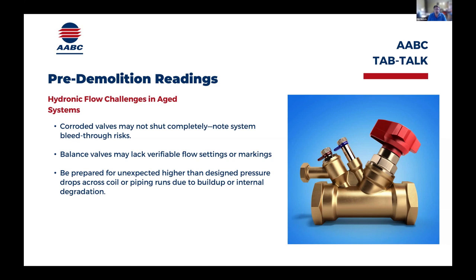Like you talked about, if the system's up and running in normal control, maybe an entering and leaving temperature of a coil along with the flow reading - if you can get both of them to match up, that's always a good thing. But there's no doubt that after 20, 30 years, there's going to be some integrity issues with the piping. Like you mentioned earlier today, the type of pipe they used 30 or 40 years ago is not exactly like they're doing now. So older equipment's definitely going to be giving you some bad readings because of the integrity of the equipment there.